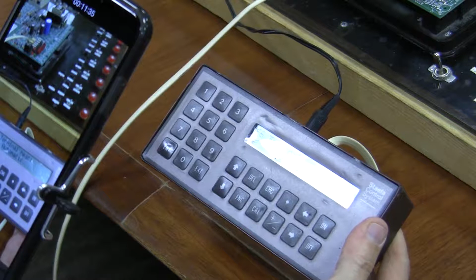Just because I'm so forgetful, I might have manualed a whole bunch of things when I got here, right? So if I hit the function button and scroll down here, there's this one called reset controller. Every time before I disconnect from a controller, assuming I'm not purposely trying to manual something, I scroll to that, hit the function box, scroll to reset, and hit enter. And as soon as I hit enter, it takes everything that was in the card that was in manual and puts it to automatic.